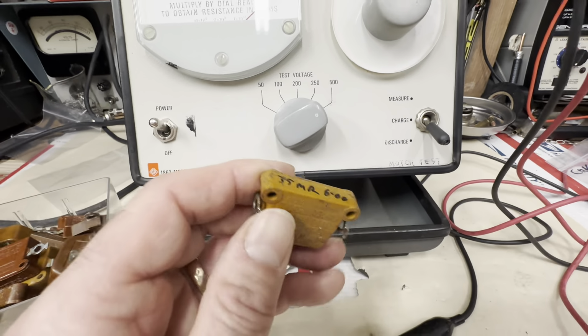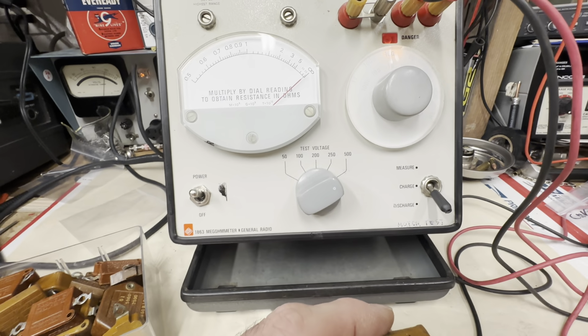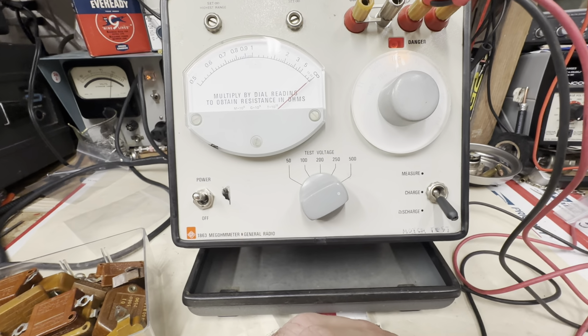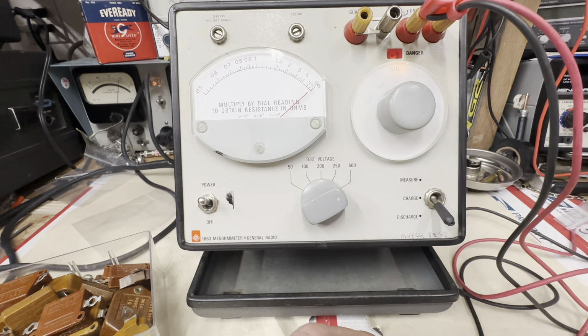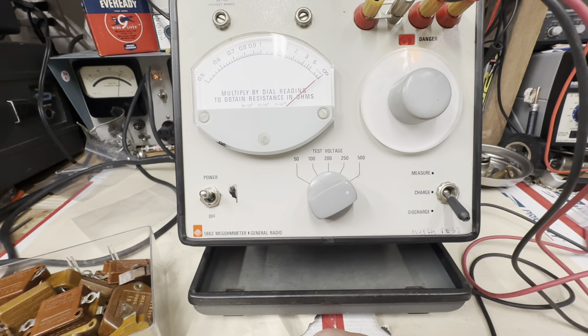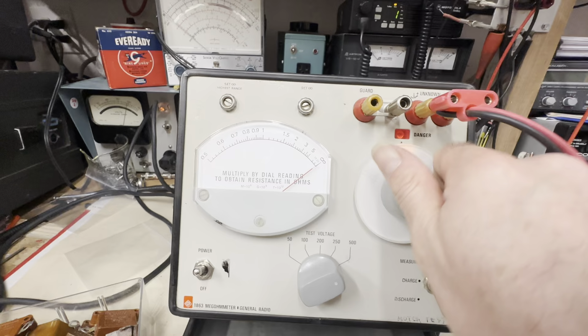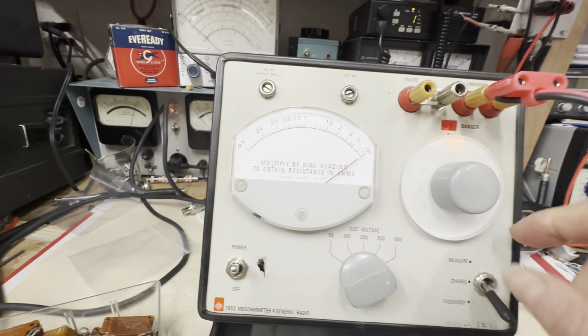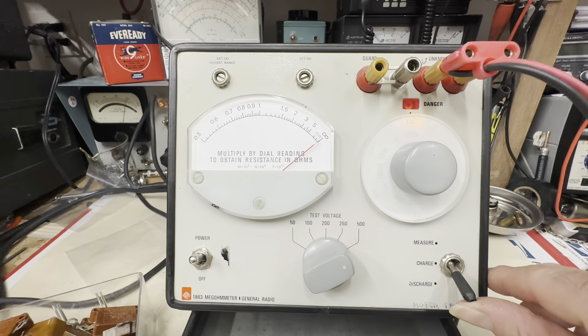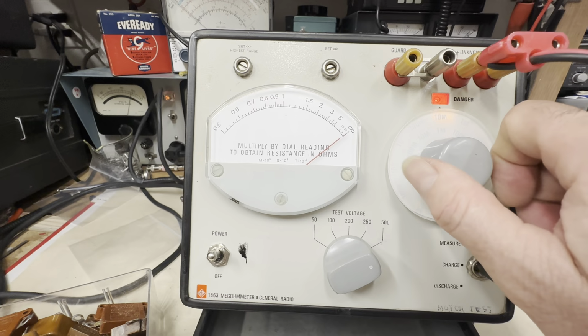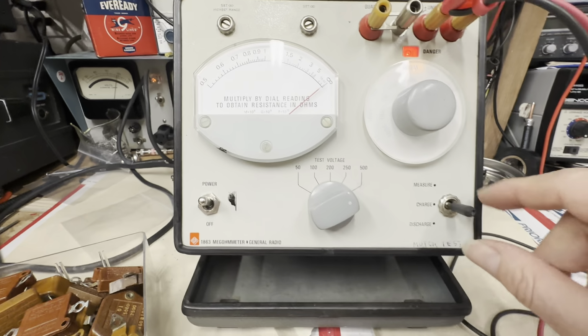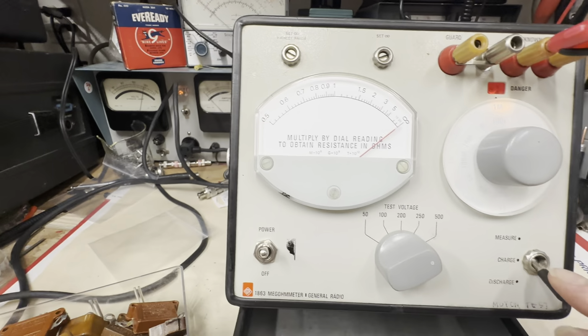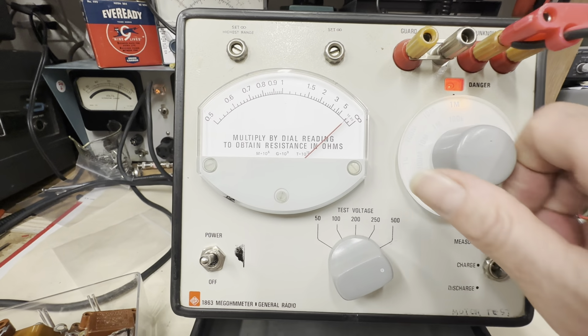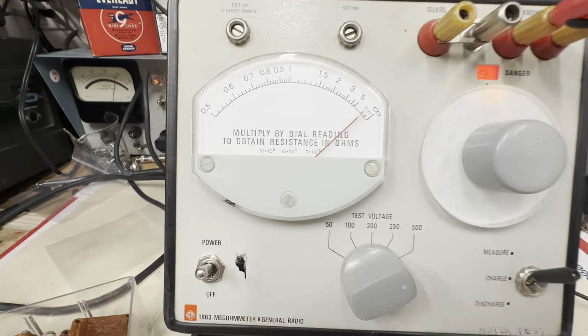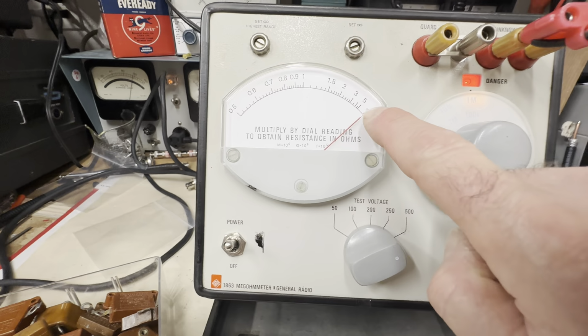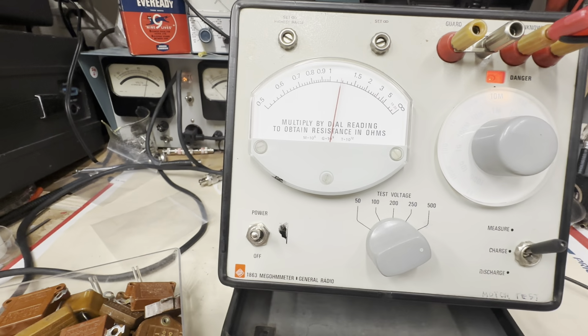And you guessed it, yes. The last time I tested it, it was on one of these GenRad testers, although it was probably the 1862 Charlie or the 1862 B as in Bravo. Okay, so if that was 35 megohms, we're going to start on the 1 megohm scale here. There we go. Saw the impulse there, and turn this thing up. And, stand by. Run it up to there. Wow, we're on the 1 megohm scale, and we're already a little over 10 megs leakage. Let's see where we're at.